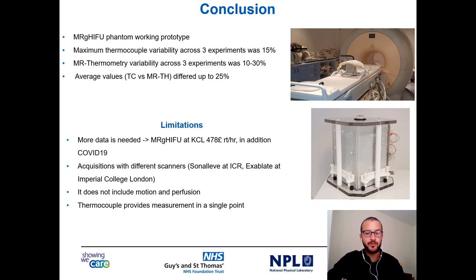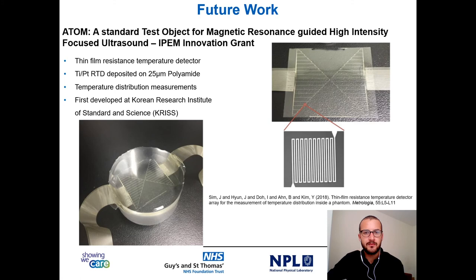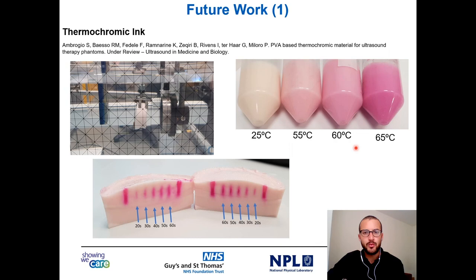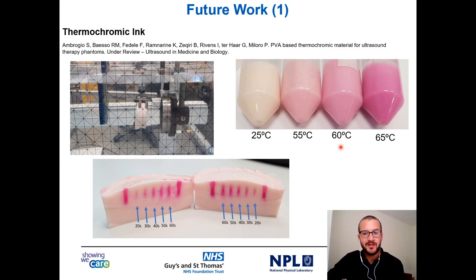It would also be nice to collect and compare data with different scanners and add to the phantom motion and perfusion, which can further challenge the machine. Thermocouples provide measurement at a single point, which is a major limitation. However, we are already moving forward and we received a grant to develop a thin film matrix array sensor for temperature distribution measurements. In addition, we have a paper under review in Ultrasound in Medicine and Biology for the development of a PVA-based thermochromic material, which changes color in relation to temperature in the region of interest of HIFU. This material is quite interesting because it can be embedded in phantoms or in 3D models.